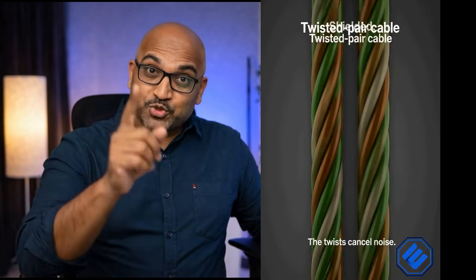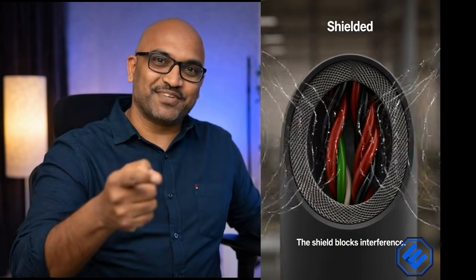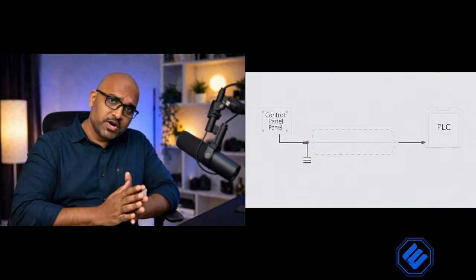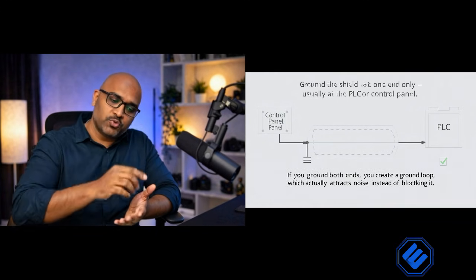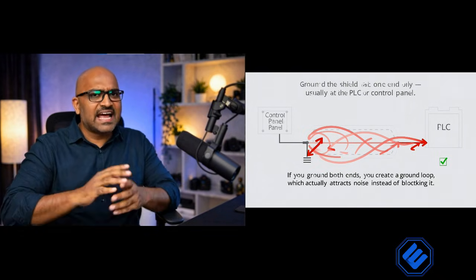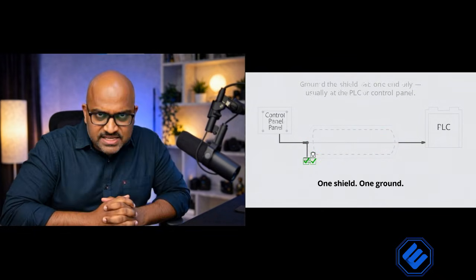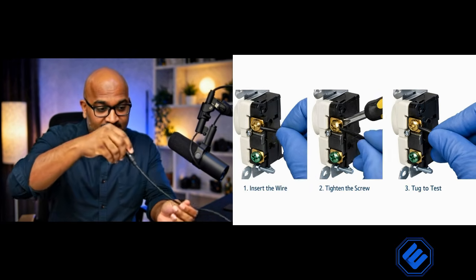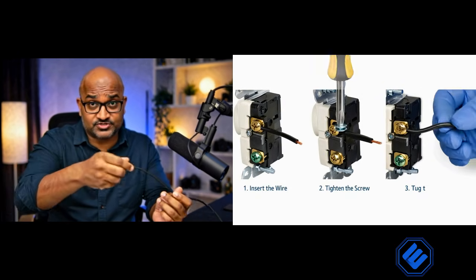For almost all analog sensors, you want a shielded twisted pair cable. The twists cancel noise, the shield blocks interference. Step 2. Ground the shield correctly. This is where people mess up. Golden rule, ground the shield at one end only, usually at the PLC or control panel. If you ground both ends, you create a ground loop which actually attracts noise instead of blocking it. One shield, one ground. Loose terminals, bad crimps, corrosion, all of these introduce resistance and intermittent faults. Every connection should be clean, tight, and secure. After tightening, give the wire a gentle tug. If it moves, it's not done. Get these fundamentals right, and you eliminate a huge percentage of sensor problems before they ever start.